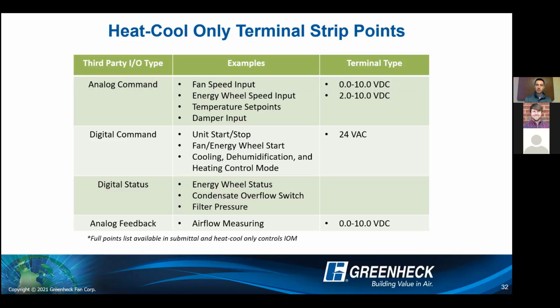As a side note, talked about the Department of Energy and the efficiency requirements. With inverter compressors, we are the only manufacturer that really allows this terminal strip type control setup. So inverter compressors are a whole different animal when it comes to controlling them and keeping them within the compressor envelope and operating that VFD. So manufacturers won't be able to provide terminal strip type controls, or those full-blown terminal strip type controls, right now. So as you're making the change over to variable speed or inverter compressors, keep in mind that this is really the only terminal strip type control on the market that allows you to utilize that with those variable speed compressors.